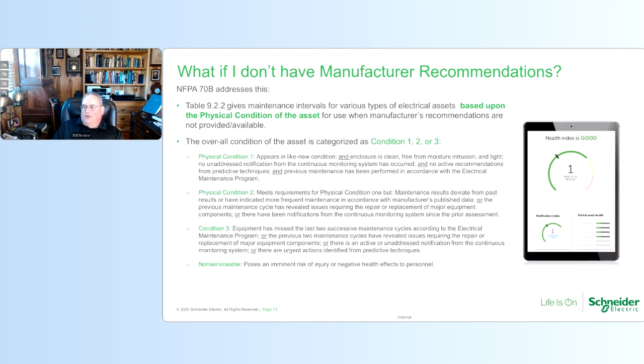The lower the condition number, the better shape the asset is in, and the longer Table 9.2.2 will allow between maintenance intervals. Condition 1 is where the equipment appears to be in like new condition, and the enclosure is clean, free from moisture intrusion, tight, has no unaddressed notification from the continuous monitoring system or active notifications from predictive techniques, and previous maintenance has been performed in accordance with the facility's electrical maintenance program. This is a high bar. This is like new equipment.